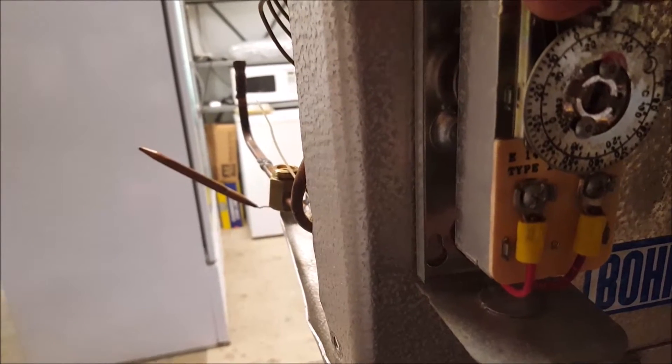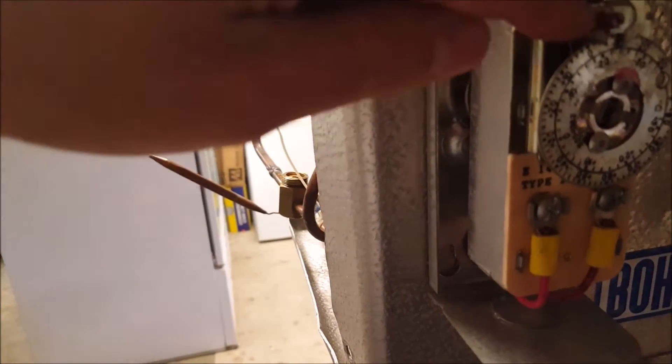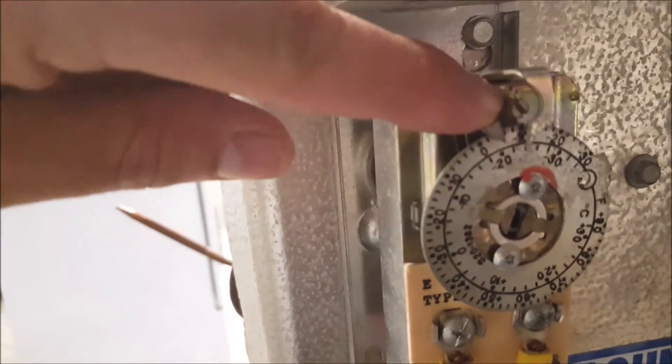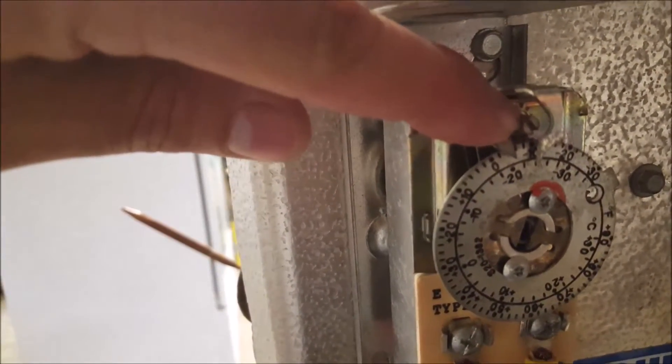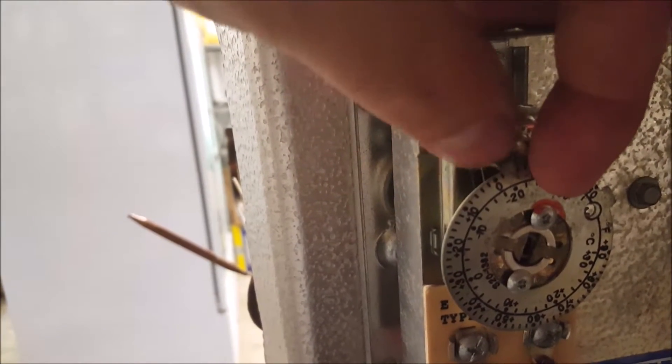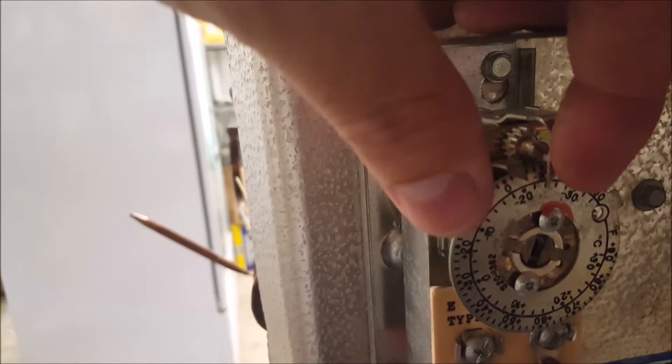These two arrows, you can change the differential by putting a flathead screwdriver right there and turning that. That's going to widen these arrows apart, mainly this arrow here, your differential, and give you either a larger differential or a smaller differential.